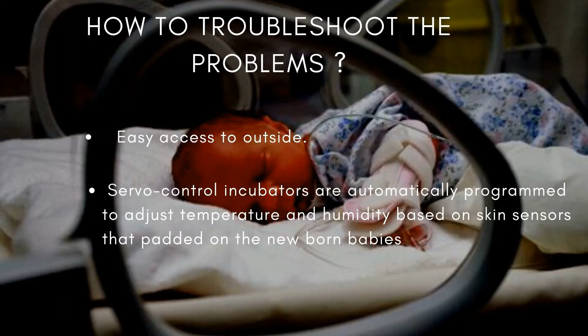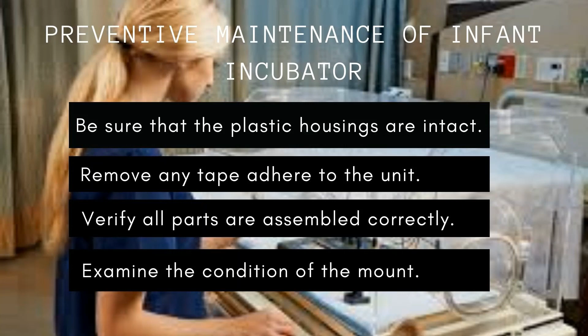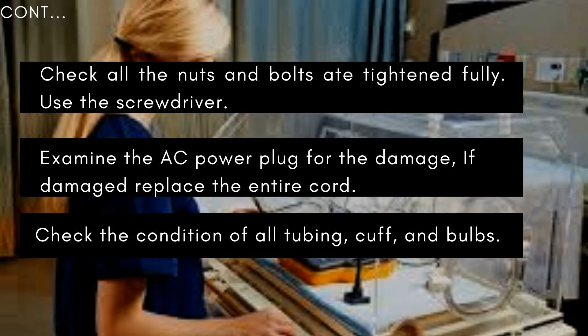Next is preventive maintenance of infant incubator. Be sure that the plastic housings are intact, that all hardware is present and tight, and that there is no serious abuse. Remove any tape adhered to the unit. Check all rubber and plastic gaskets in the unit. Verify all parts are assembled correctly, as misassembly of internal components would interfere with performance. If the device is mounted on a stand or a cot, examine the condition of the mount. Check that all nuts and bolts are tightened fully, using the screwdriver. Examine the AC power plug for damage. If damaged, replace the entire cord. Check the condition of all tubings, cuffs and bulbs.